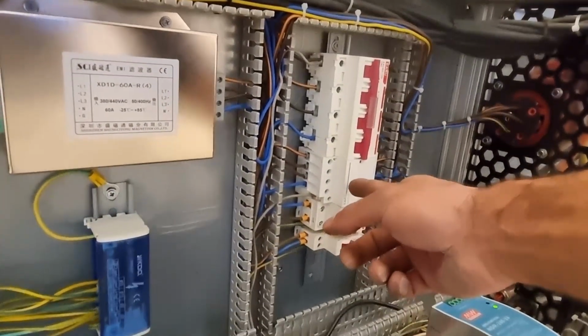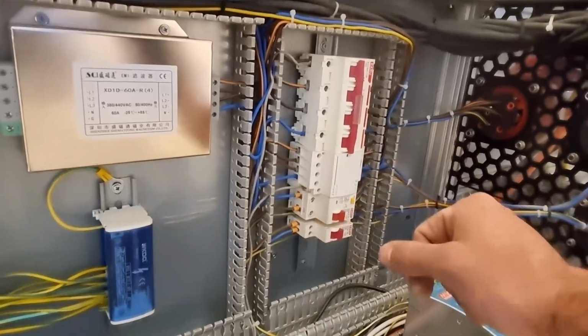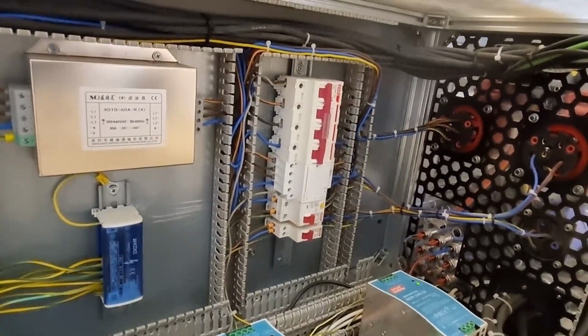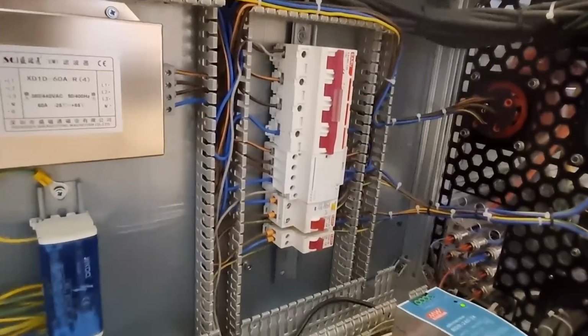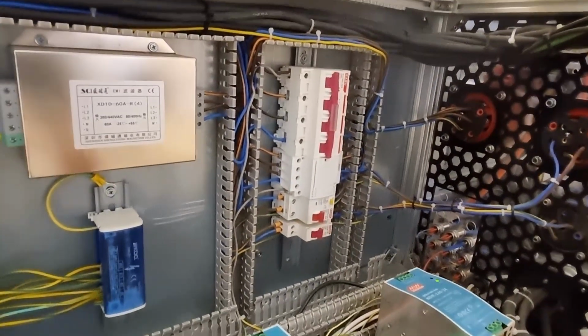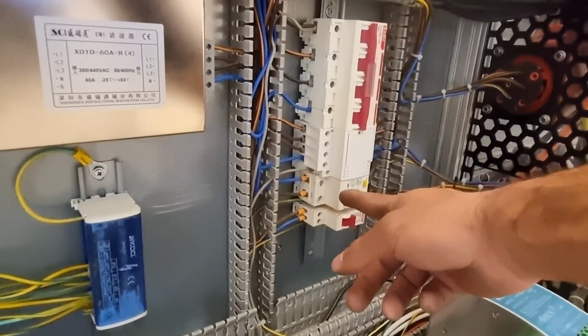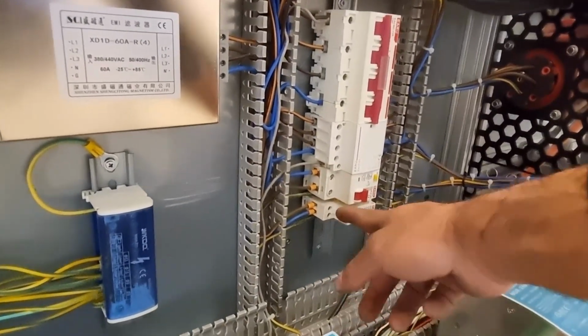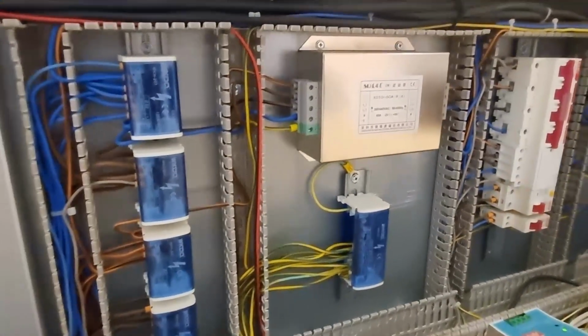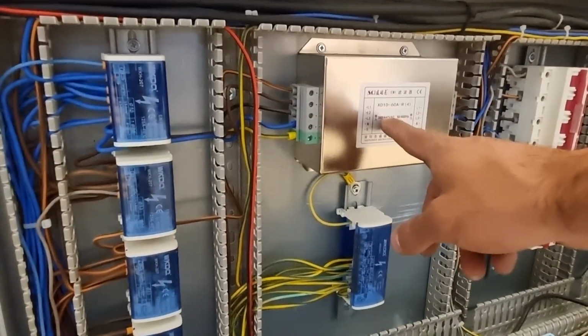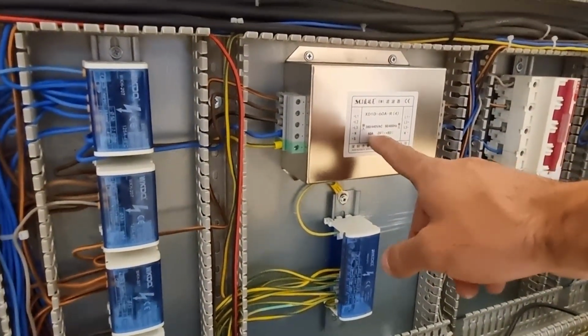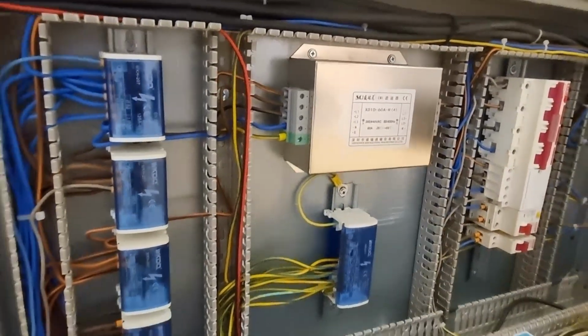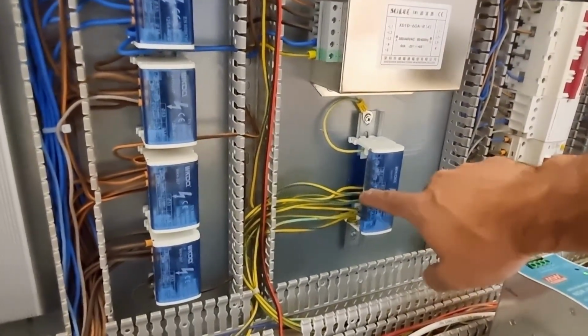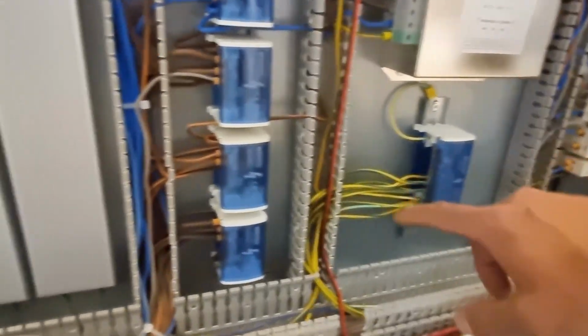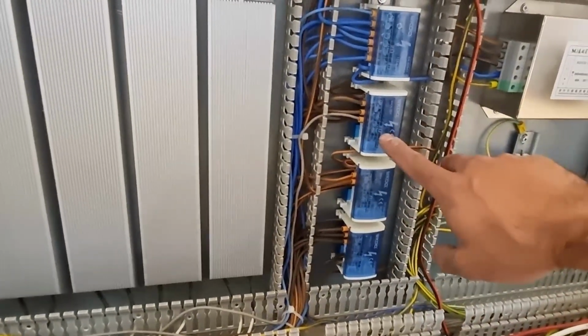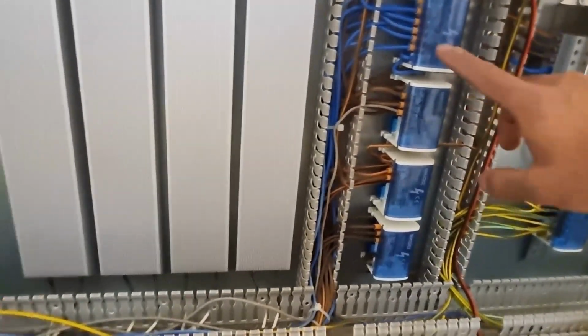Sorry, I forgot a word - this is the contactor for the main power on and off of the electrical cabinet. Breaker for the laser source. Breaker for the water chiller. This is a 60 amp line filter, EMI filter, 3-phase 60 amp. This is a terminal block for all the ground wiring, and terminal blocks for all the phases and for the neutral.